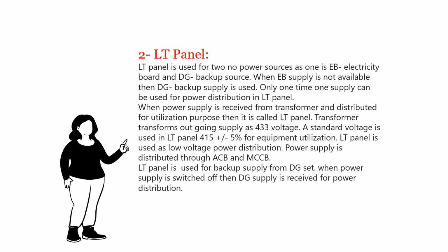Transformer outgoing supply is 433 volts. A standard voltage of 415 volts plus or minus 5% is used in LT panel for equipment utilization. LT panel is used as low voltage power distribution. Power supply is distributed through ACB and MCCB. LT panel is used for backup supply from DG set. When power supply is switched off, then DG supply is received for power distribution.